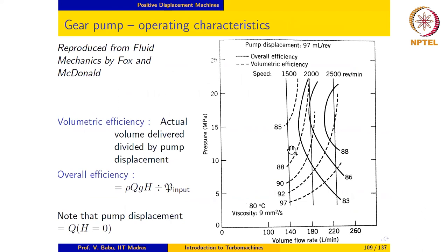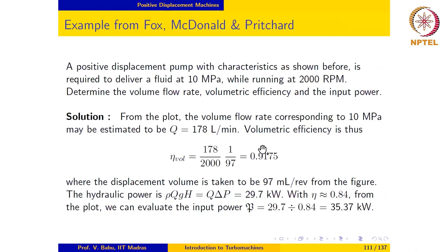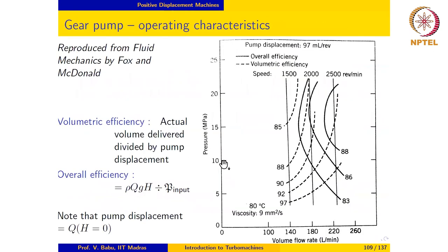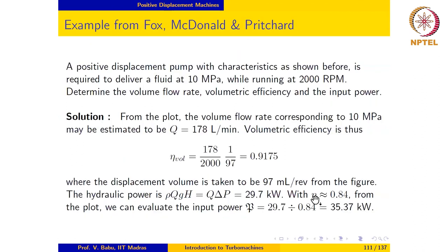To calculate the input power, the hydraulic power is given by rho times Q times g times H. Note that rho times g times H equals delta P, so hydraulic power equals Q times delta P, which works out to 29.7 kilowatts. Going back to the characteristic at delta P of 10 MPa and 2000 RPM, the overall efficiency is roughly 84%. Therefore the input power equals 29.7 divided by 0.84, which gives approximately 35.37 kilowatts.